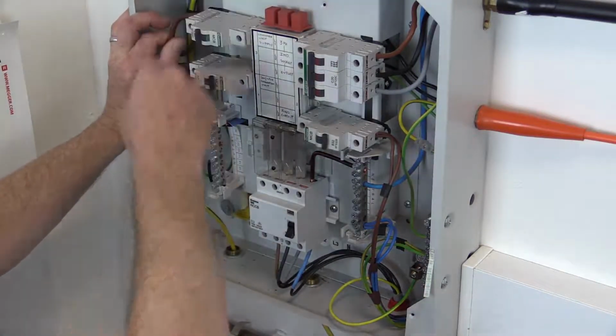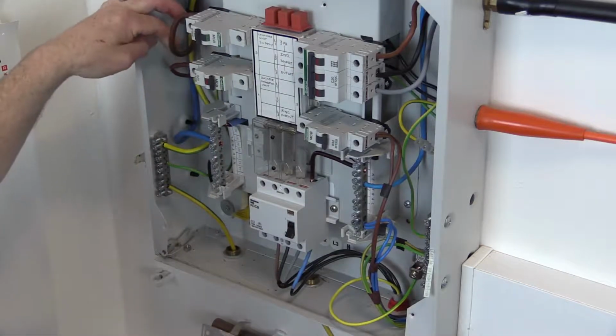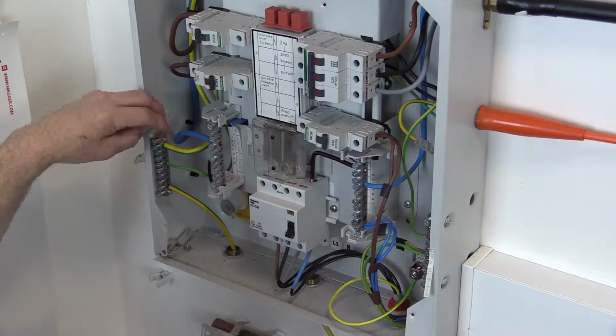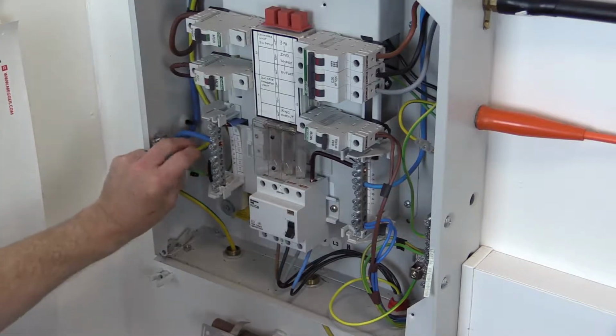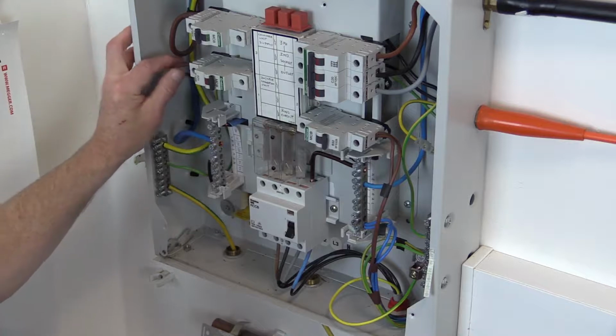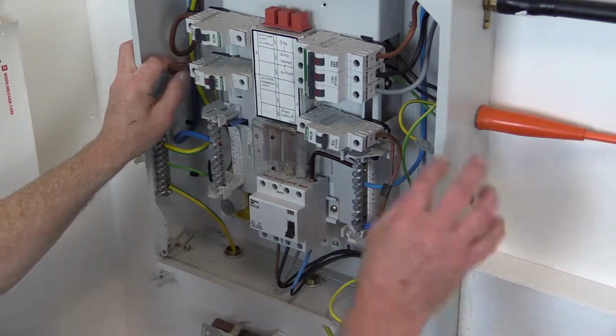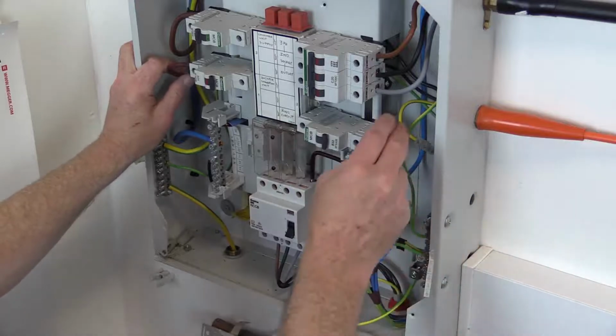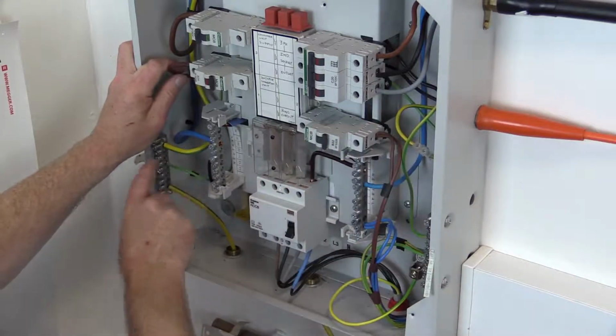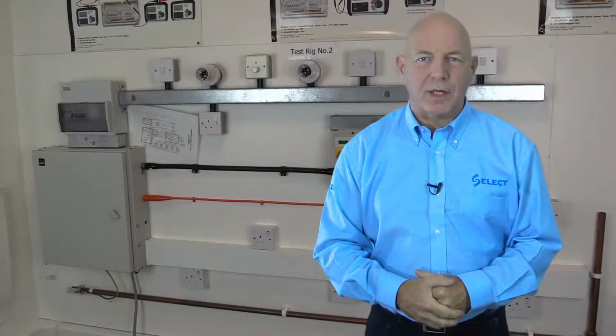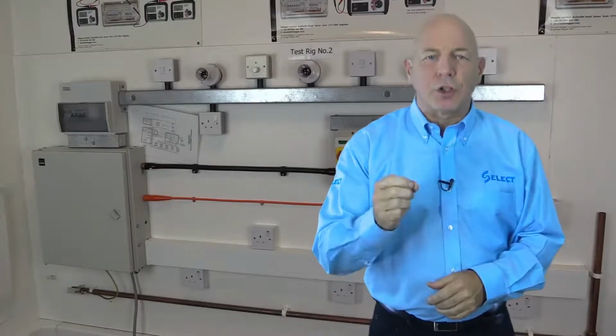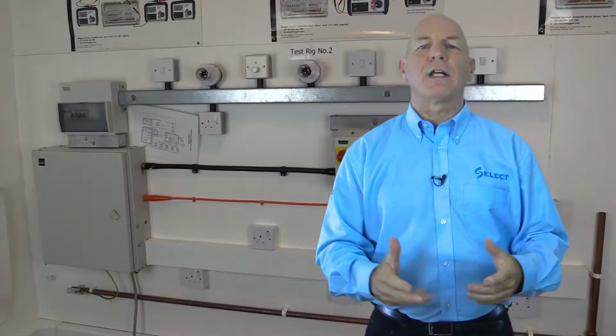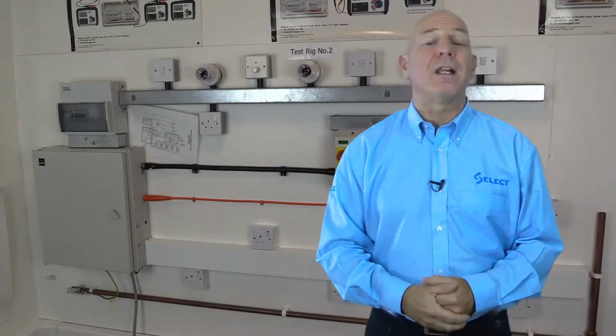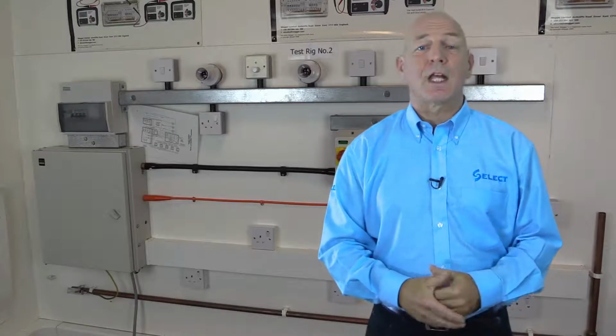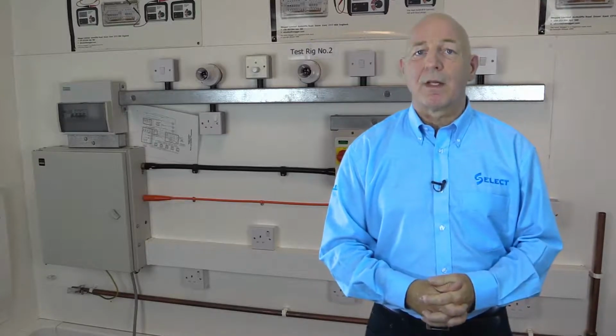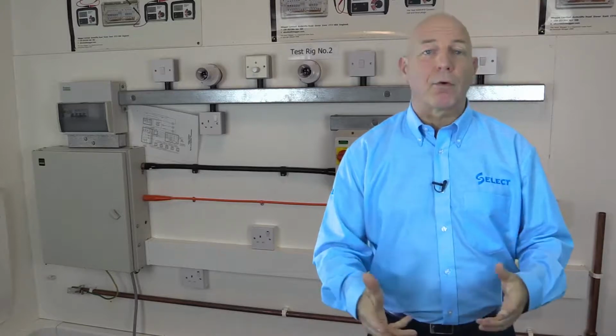This would normally be included with installation layout drawings, circuit charts and cable schedules, tables, etc., and is of particular importance to the inspector who will be comparing subsequent test results against various criteria contained within BS 7671 to establish compliance with the design. Regulation 611.3 provides a list of items that should be checked where relevant, including as appropriate all particular requirements for any special installations or locations, as per Part 7 of BS 7671. E.g. location containing a bath or a shower.